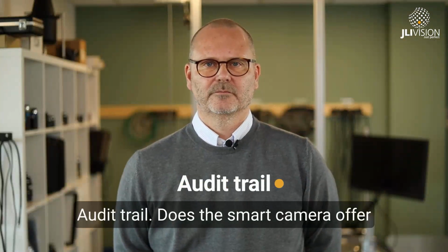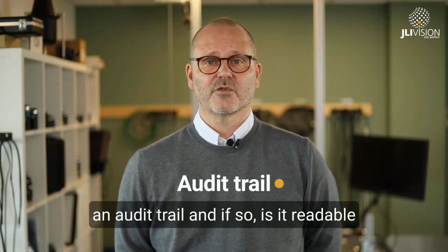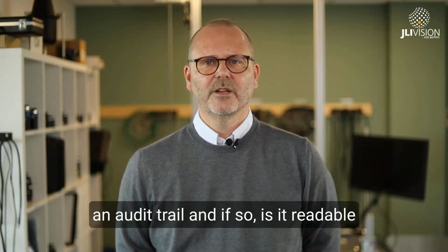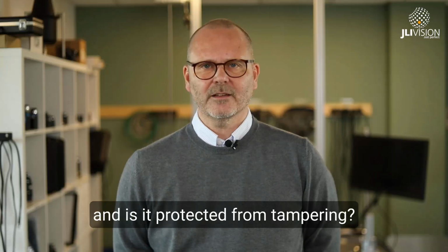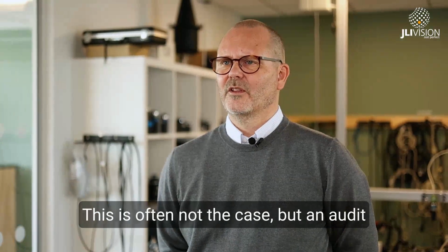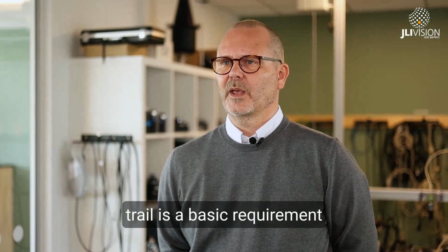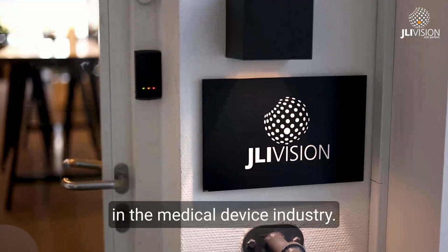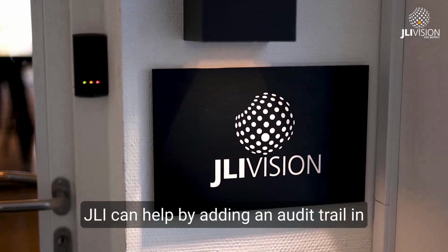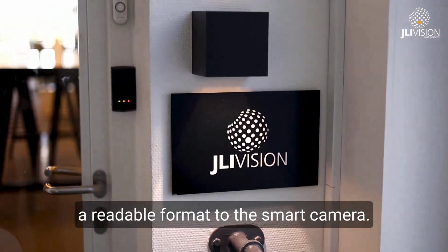Audit trail. Does the smart camera offer an audit trail? And if so, is it readable? And is it protected from tampering? This is often not the case, but an audit trail is a basic requirement in the medical device industry. JLI can help by adding an audit trail in a readable format to the smart camera.